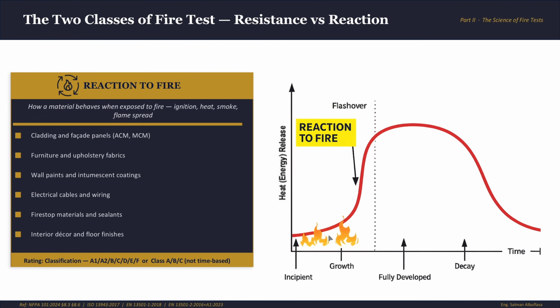Here, in the incipient, ignition, growth phase, all the way to flashover. Right around here where this line is, this is where reaction to fire matters. It's measured by classification, not time-based. Why? Because the materials never fail in a typical time-failure sense. Their performance is qualitative and not a countdown. Let's take a curtain for example. I cannot say the curtain can stand the fire for 10 minutes. It doesn't make sense. But a door can. We'll get to that later.